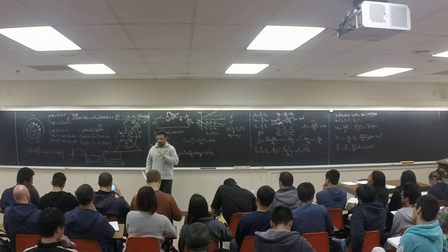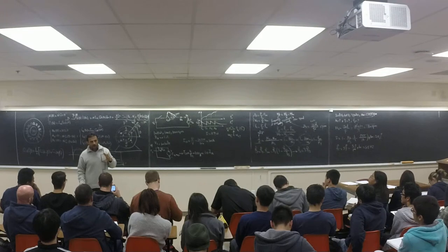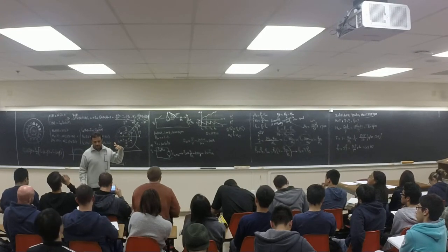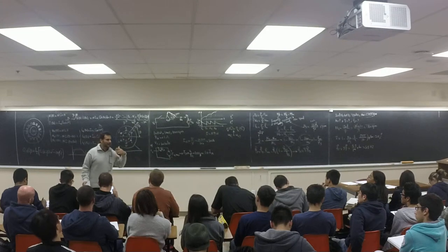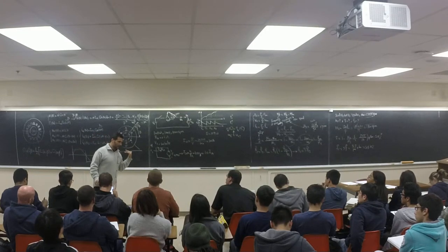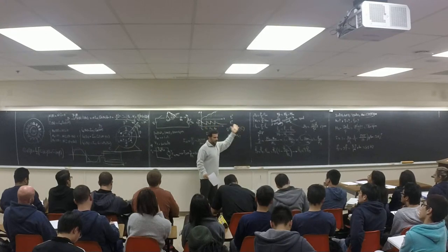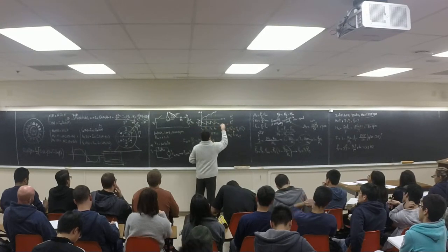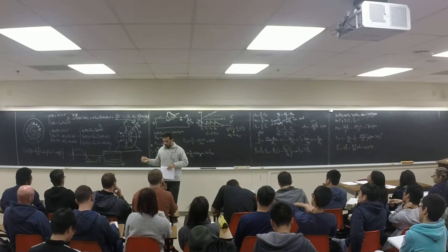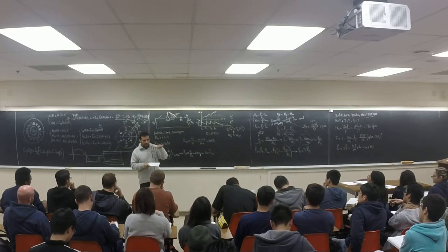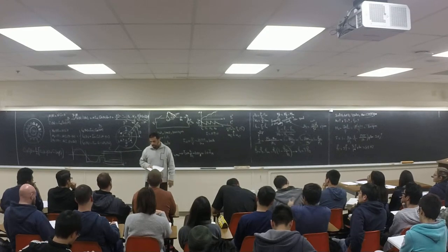So the question is asking us to design a starter. Basically, the armature current maximum will be 2IN, and it doesn't say the minimum. The armature current will be limited between IN and 2IN during the startup. Here, maybe the load is less than the nominal. Maybe it comes down here. It doesn't have to start at IN. Or maybe even no load, there is no current at all, right? But during the startup, we want to keep the current between 100% to 200% of IN, right?